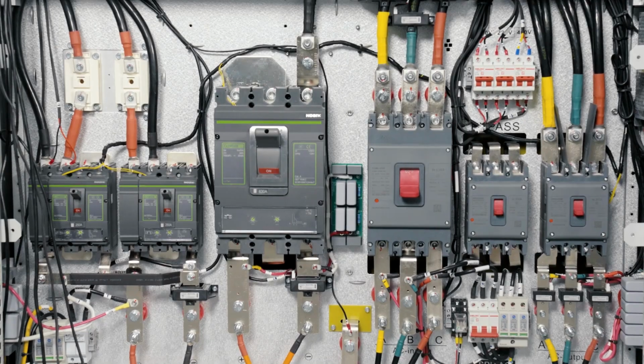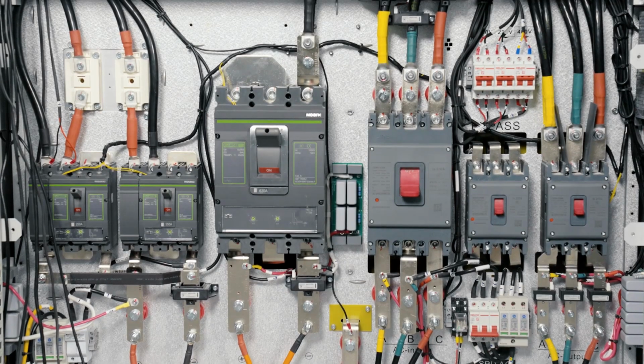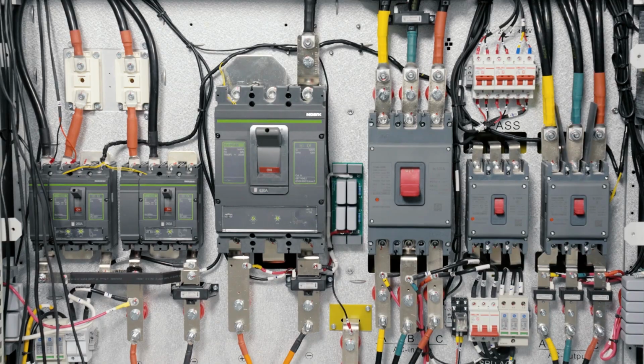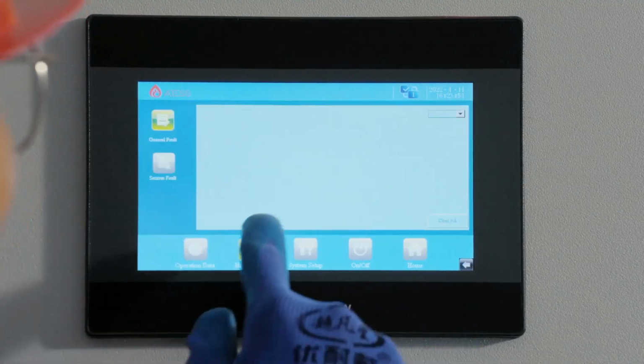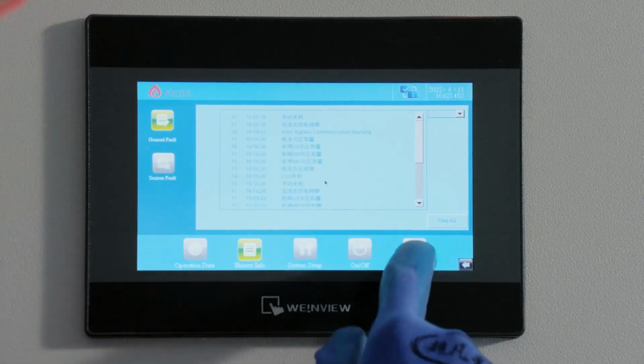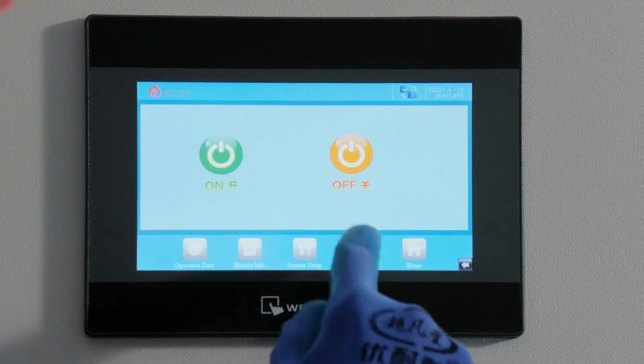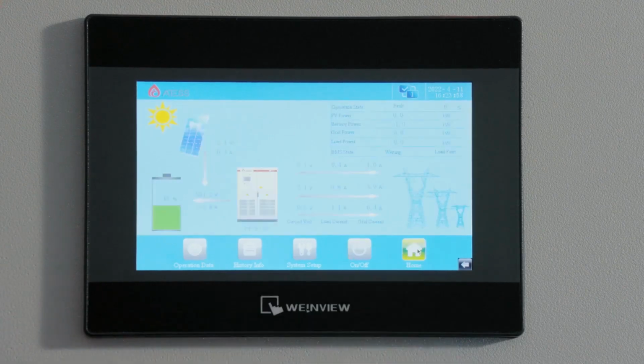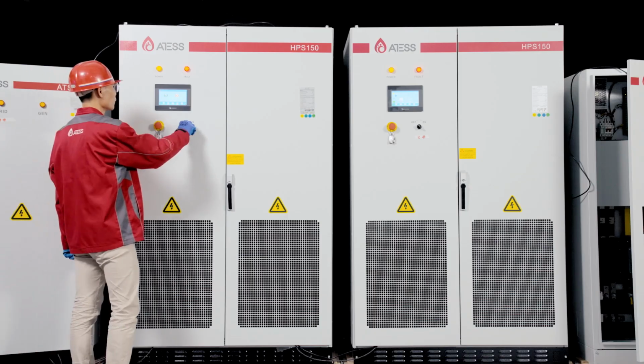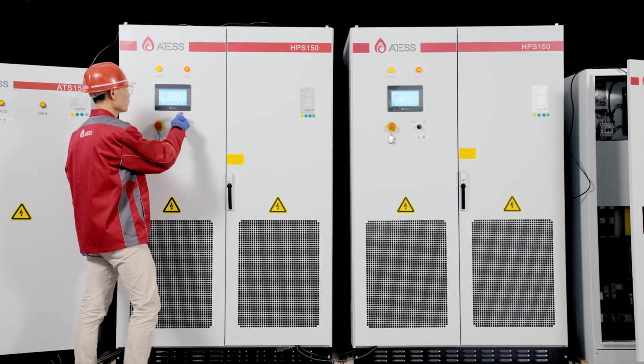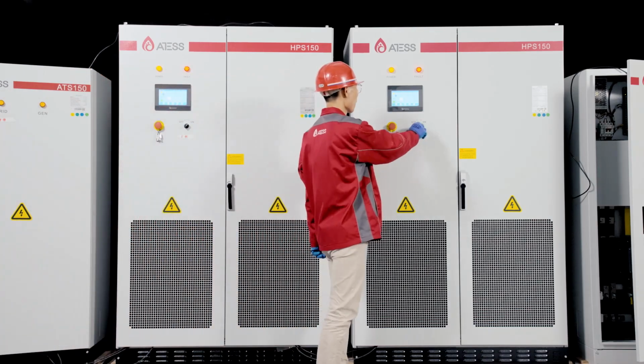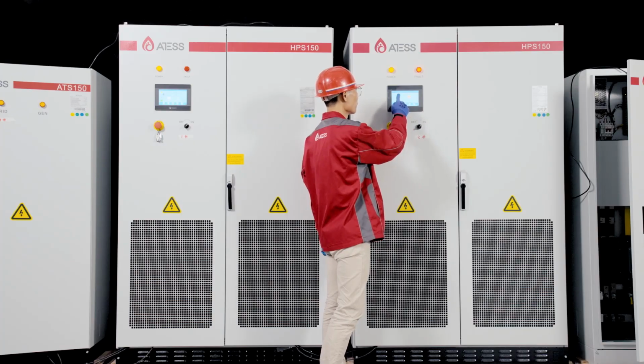For the 2 HPS, ensure that only the PV breaker and battery breaker are closed, and the other breakers remain disconnected. Check the fault information page of the 2 HPS. If no fault information is displayed, run the 2 HPS. If there is a fault, contact ATESS. Turn the black switch knob to on and click the power button on the screen to run the 2 HPS.